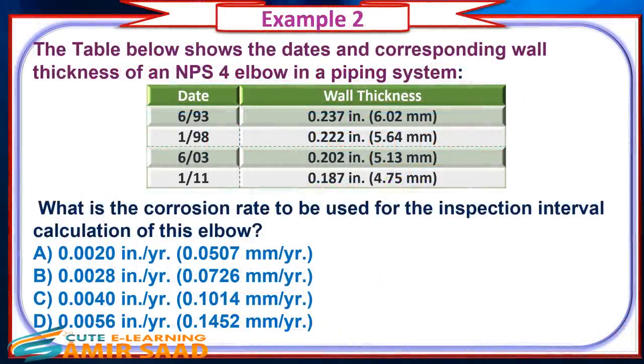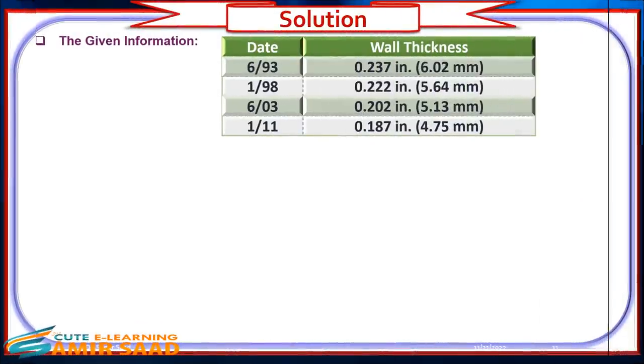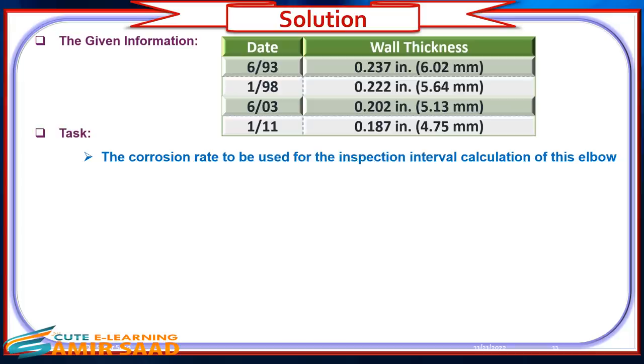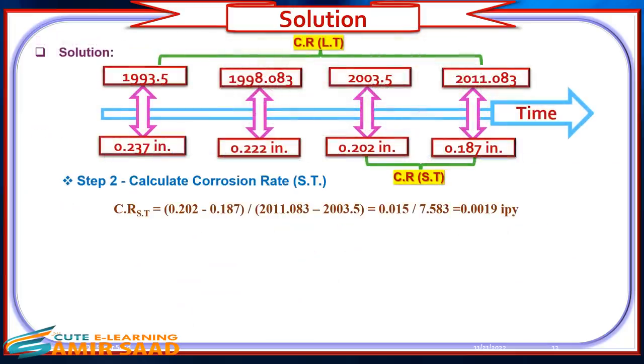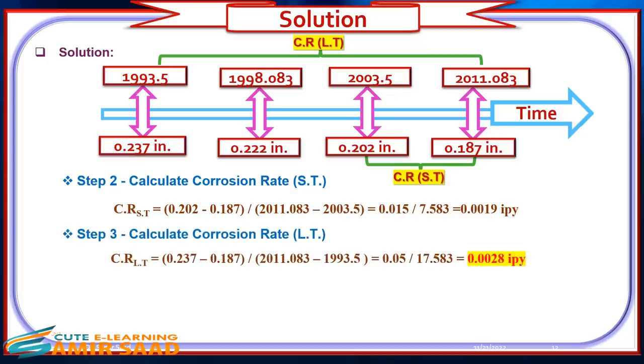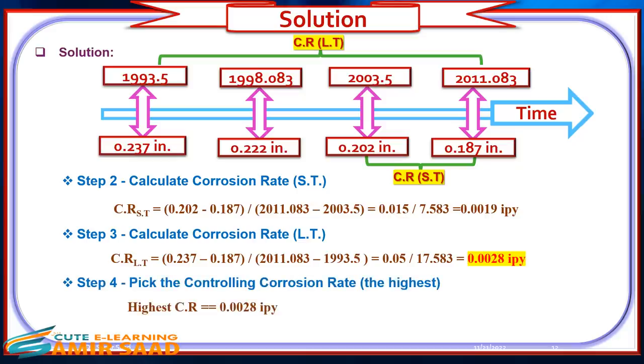Example 2: The table shows the dates and corresponding wall thickness of a nominal pipe size 4 elbow in a piping system. What is the corrosion rate to be used for the inspection interval calculation? Solution: Step 1: Convert months to years. Step 2: Calculate the short-term corrosion rate. Step 3: Calculate the long-term corrosion rate. Step 4: Pick the controlling corrosion rate — the highest. The answer is B: 0.0028 inch per year.